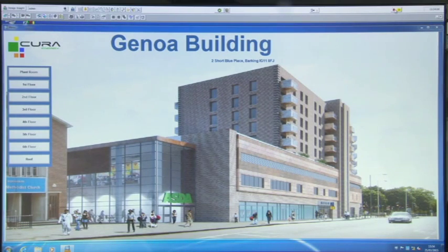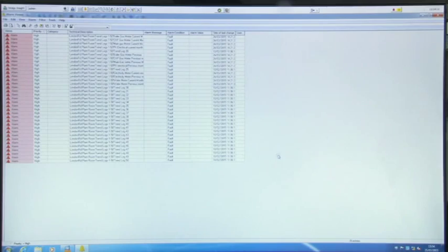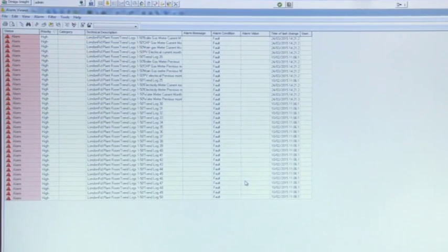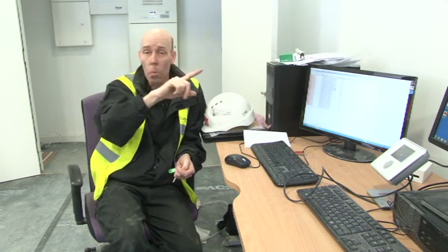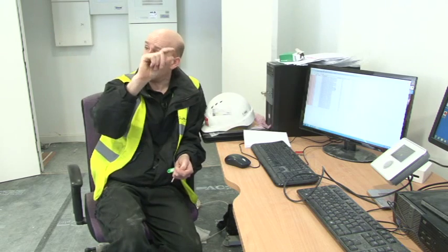On here, there's a number of sample alarms. So those are the alarm charts as you would probably get. On here it says boiler gas meters exceeded a high limit and is in fault, and these are all the ones that were the test alarms just to prove that the system worked. But that's basically what you get, like an Excel spreadsheet displayed on the screen which will tell you when it occurred, the date it occurred, the time it occurred, whether it required an acknowledgement and who acknowledged the alarm.